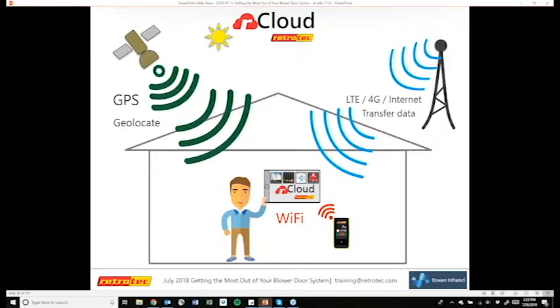And you can choose what standards you're testing to. So if you're a HERS rater, you can say, I'm testing to the ResNet 380 standard. And it'll go ahead and pull that up. Before you run your test, you can choose whether you're doing a single point or a multi-point test. And this is where the big difference is, because before this type of technology was out, it was nearly impossible to run a proper multi-point test in the field without having to do a bunch of extra math. And so now this does all that for you. You know when to change rings, you can pause the test, adjust your ring setup or your range plug setup, and then resume the test. And so now this makes multi-point tests really easy.